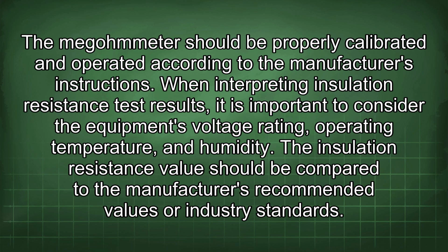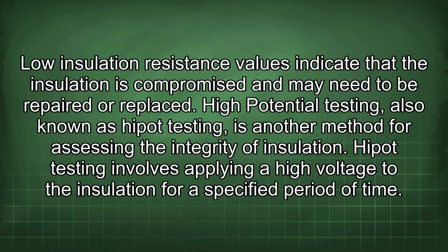When interpreting insulation resistance test results, it is important to consider the equipment's voltage rating, operating temperature, and humidity. The insulation resistance value should be compared to the manufacturer's recommended values or industry standards. Low insulation resistance values indicate that the insulation is compromised and may need to be repaired or replaced.